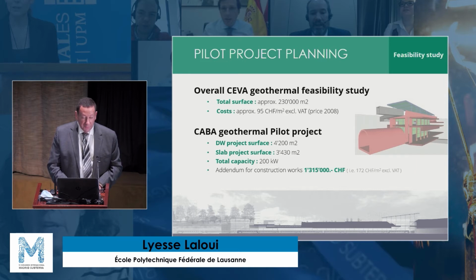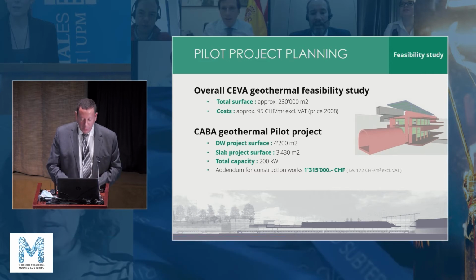So we will have diaphragm walls with a surface of 4,200 square meters, and a slab with a surface of 3,400 square meters. This is the entire area that is equipped as heat exchanger, giving a capacity of around 200 kilowatts.